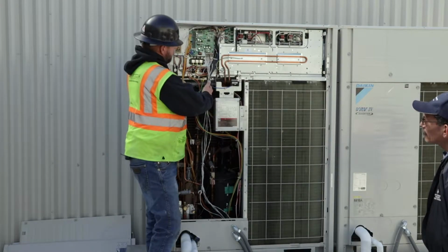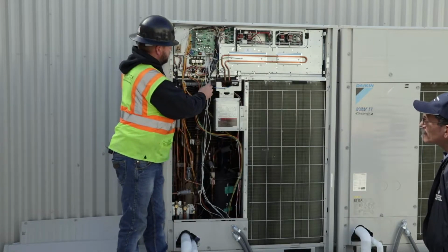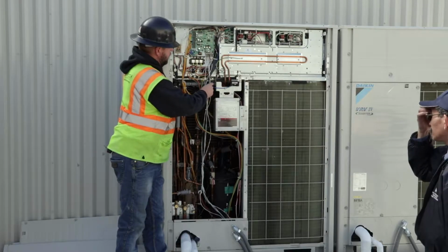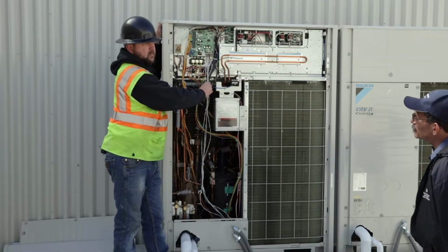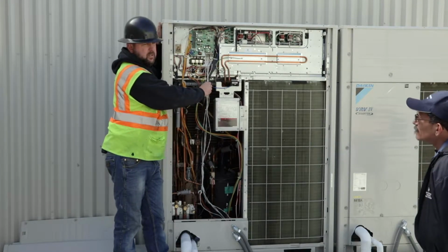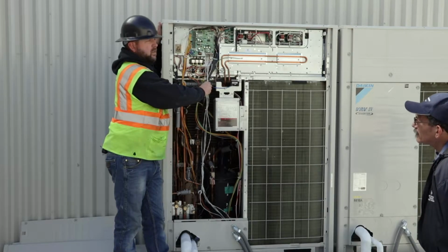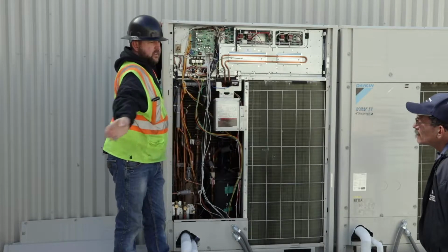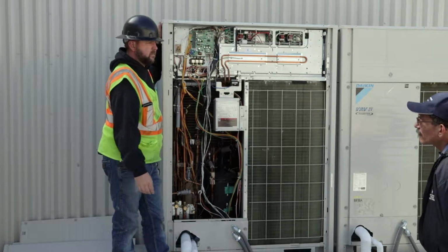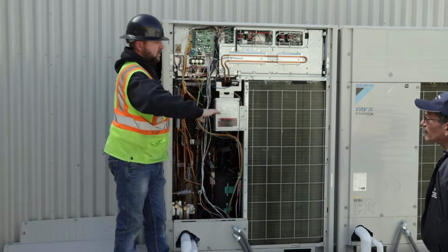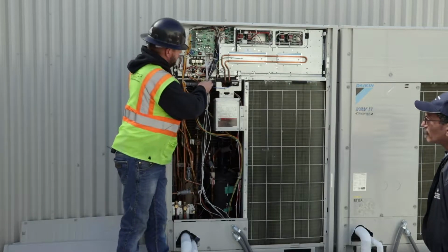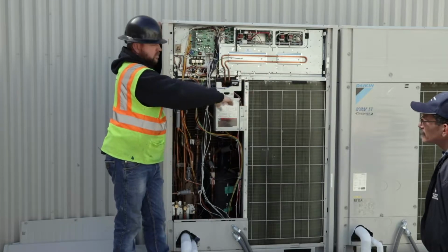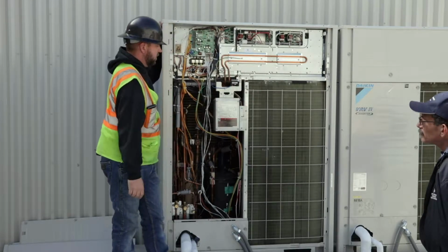These are your communication wires coming in. This one is going to all your fan coils, talking to your fan coils. This one is your communication wire between all your condensers in the building. So you've got 1, 2, 3 other condensers that this is talking to, and then it goes back to your iTouch manager down on the first floor, so it can see all your fan coils. This one is a wire just between these two that are talking.